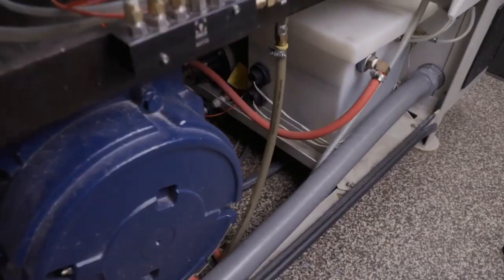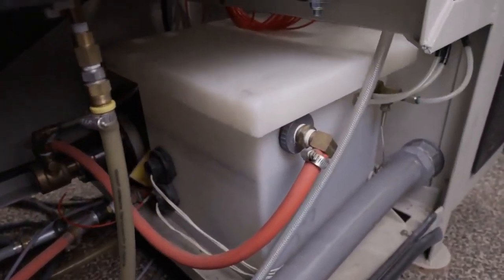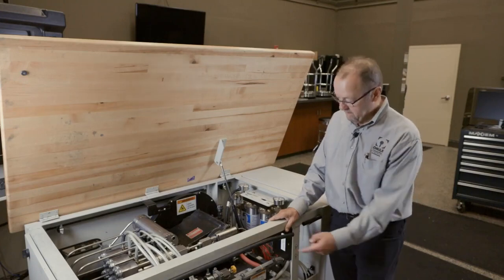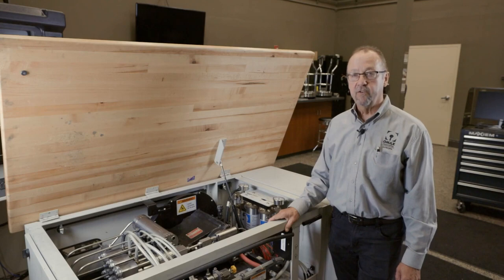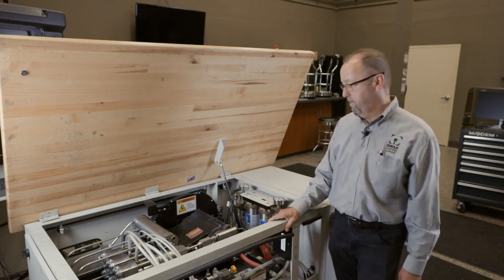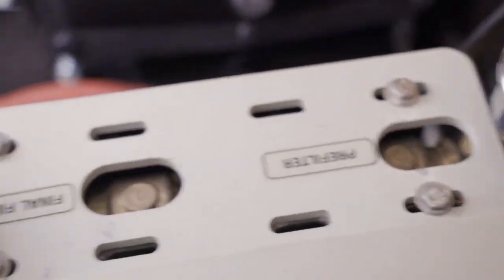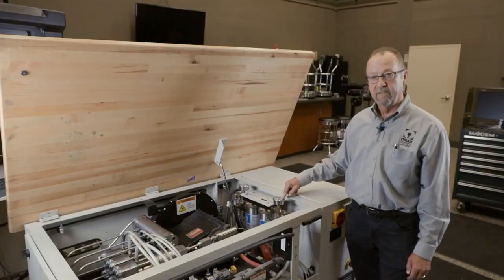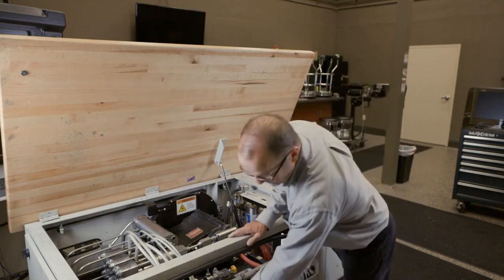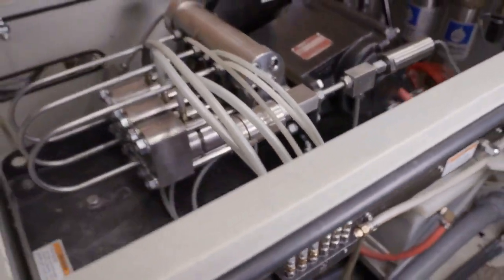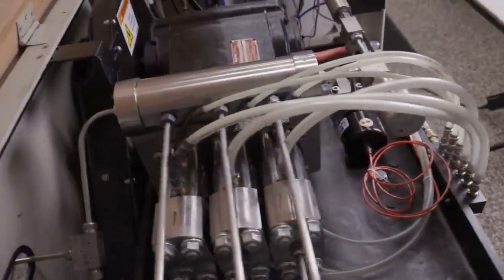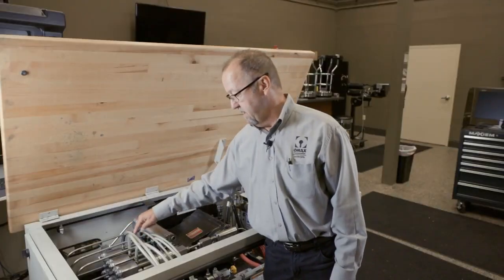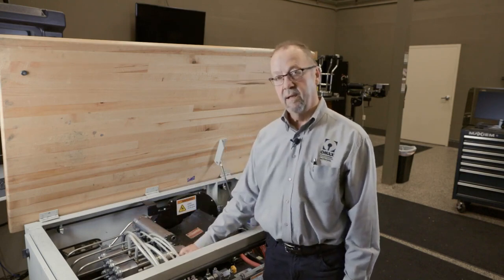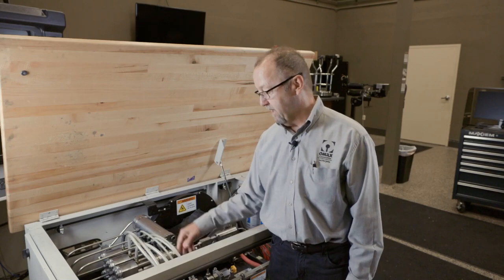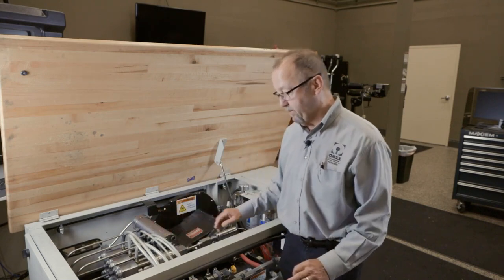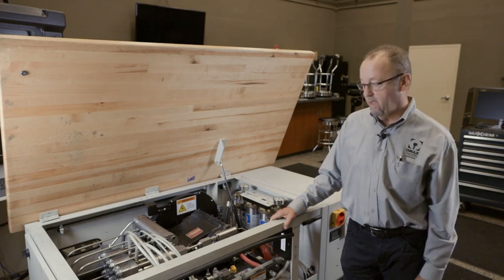Underneath here is a charge pump. We take inlet water, real small amount. We only use about a gallon a minute of water. It comes into that charge pump, gets pressurized to about 175 psi, comes through 2 filters, a 1 micron and a 0.45 micron filter. It comes out of those 2 filters into a distribution block. 6 lines coming off the distribution block. 3 of them go to check valves on the wet end, and then 3 of them we use a little bit of that pressurized water for cooling and lubricating. There's a coolant housing here that keeps that ceramic plunger and our dynamic seal cool and lubricated.